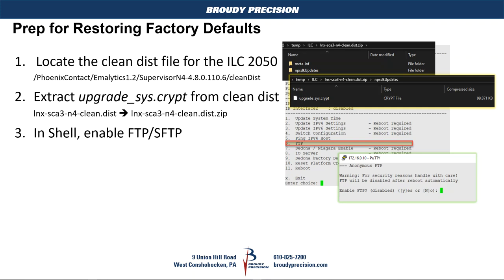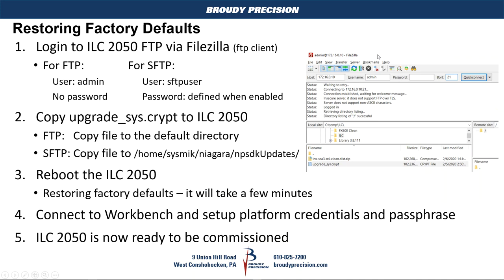The next step is to enable FTP or SFTP, depending on the level of software versioning in the ILC 2050. On the unit being demonstrated here, the option is FTP, so you would enable FTP to be able to use FileZilla to copy the .crypt file into the controller. When logging into FileZilla with FTP enabled, use the username 'admin' with no password. If you've enabled SFTP, the username is 'sftp user' and the password is what you defined when you enabled SFTP.